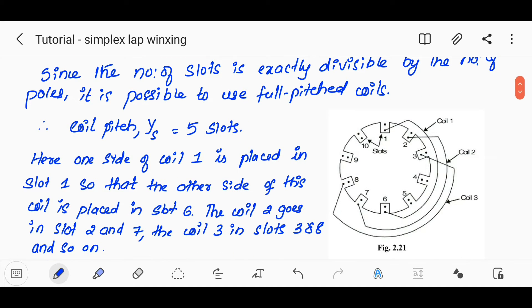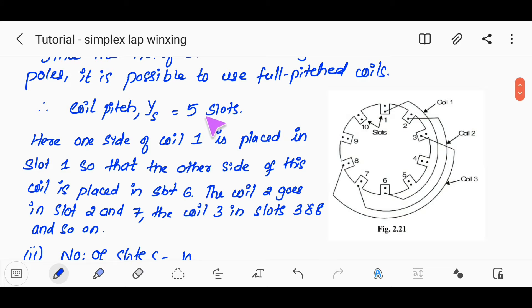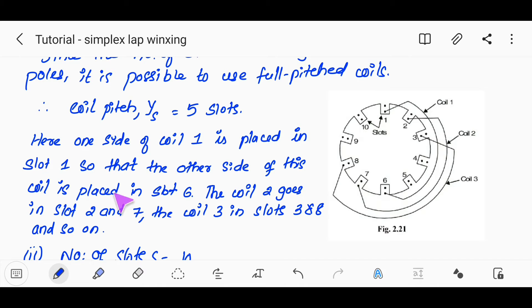We will use full-pitched coil, ensuring coil pitch is equal to 5. For the placement of coils, if you have coil side in slot 2, the other side goes to slot 2 plus 5 equals slot 7. That is our first case.